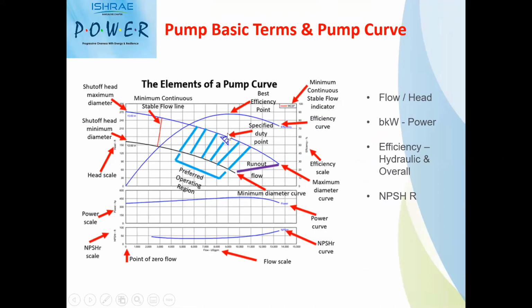For example, this is the duty parameter. So when we select the duty parameter, a particular size of the pump is selected, and it will have fixed impeller sizes. See, this is the minimum impeller size, this is the maximum impeller size of a particular pump, which is selected for your duty parameter.